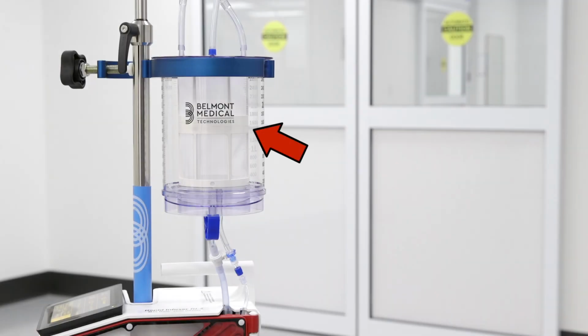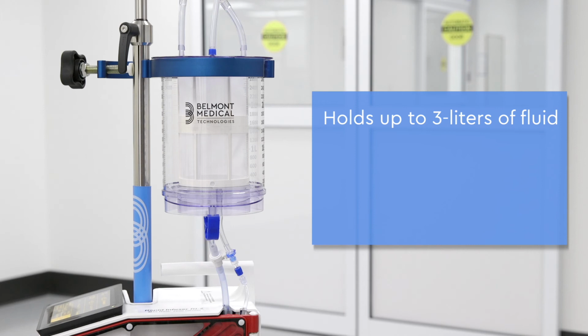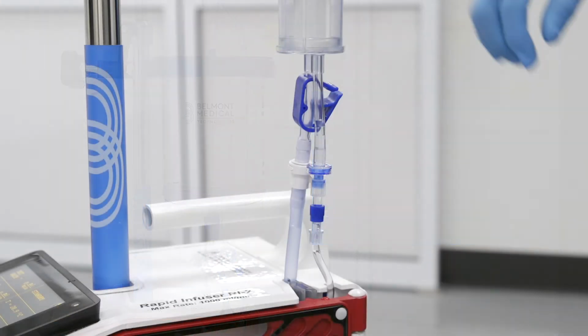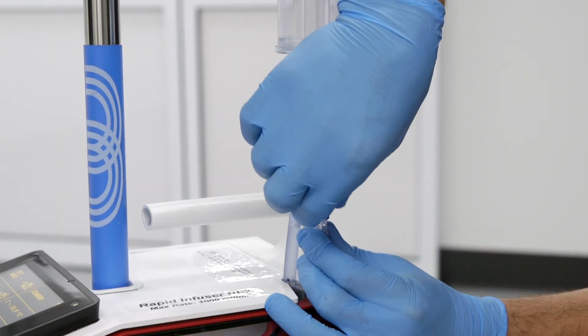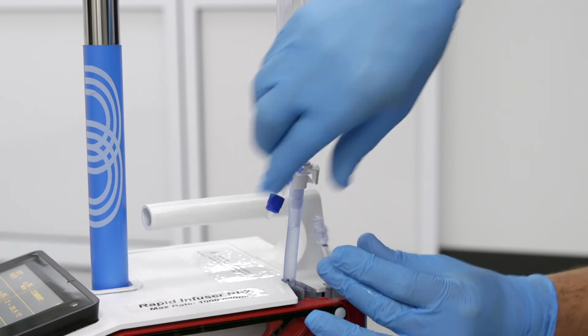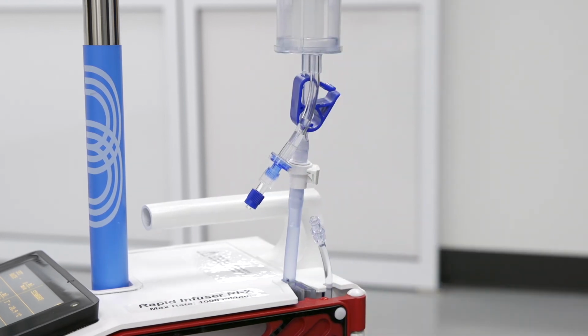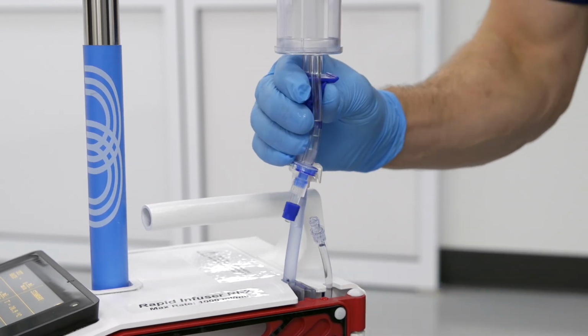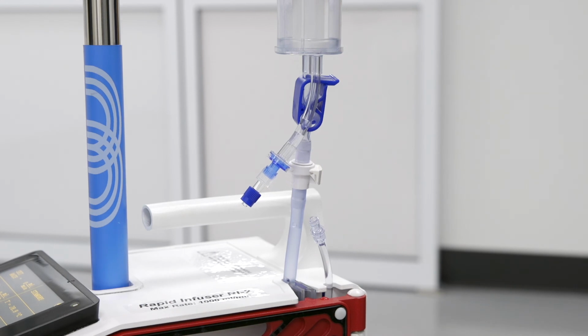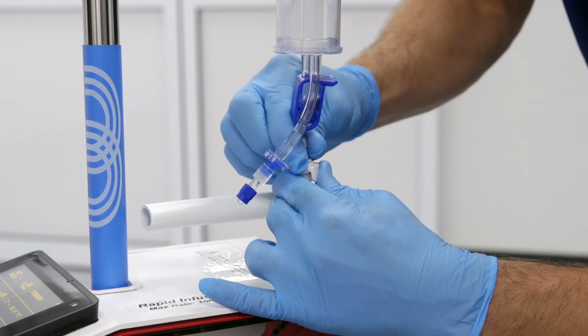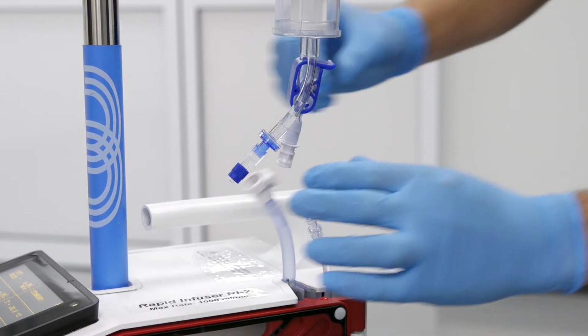The optional large volume reservoir can be added at the beginning or anytime during the procedure. The LVR will hold up to 3 liters of fluid, has 5 fluid spikes, and can be added to the system in less than 1 minute. Disconnect the small reservoir by unscrewing the lower fitting on the recirculation line. If the small reservoir contains fluid, close the blue clamp to prevent a spill before disconnecting the fluid line. Disconnect the fluid line by pressing the quick release tab while separating the fluid tubing.